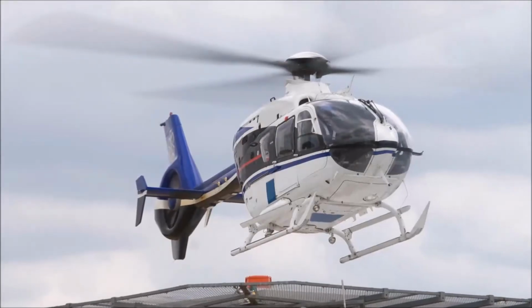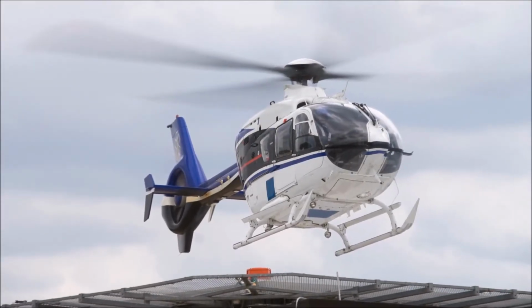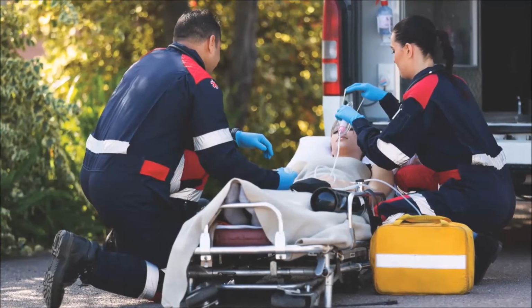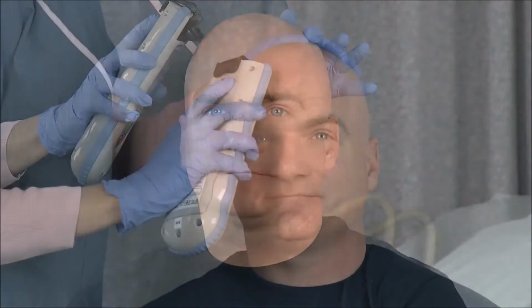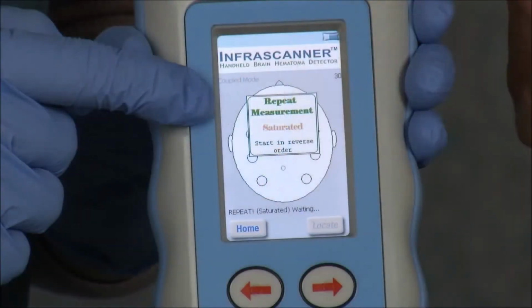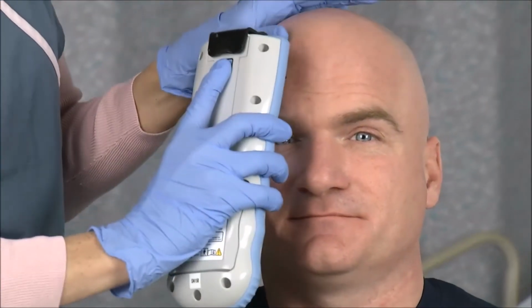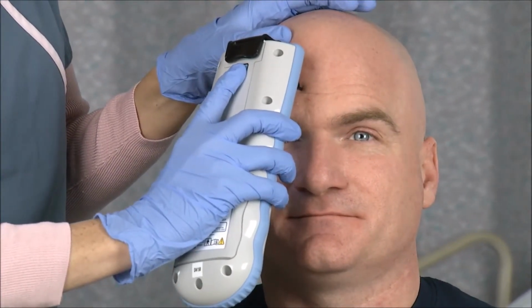If you are in an area where you cannot hear the beep or see the screen flash, such as the scene of a trauma or in bright sunlight, simply count to 10 for the first measurement and count to 6 for the second measurement. A double beep at the end of the scan indicates an error. If you hear this, check the screen and follow the error code. Press the center round green button to clear the error message and rescan. You will repeat the same procedure to collect a total of 8 scans from the 8 designated measurement locations discussed in the measurement points section.